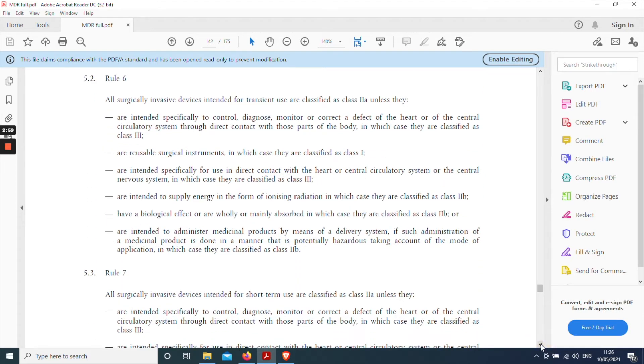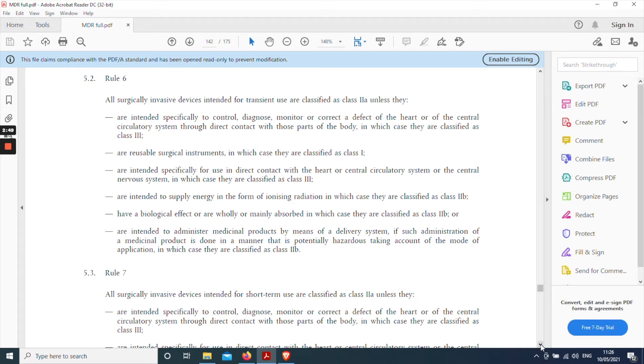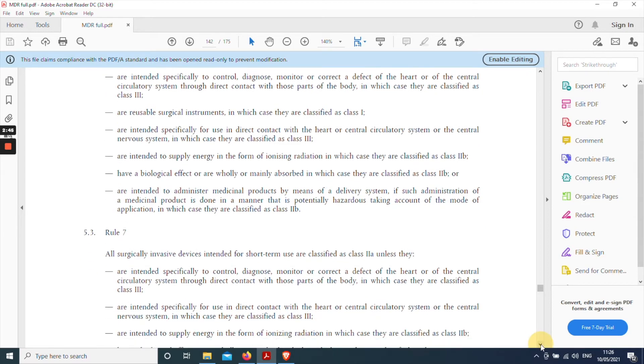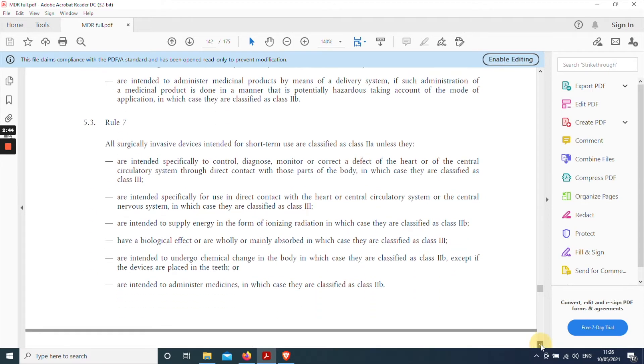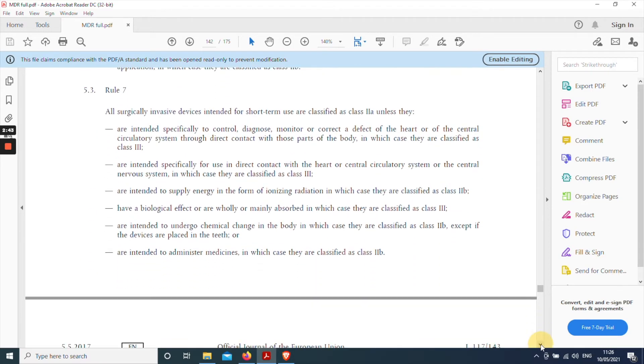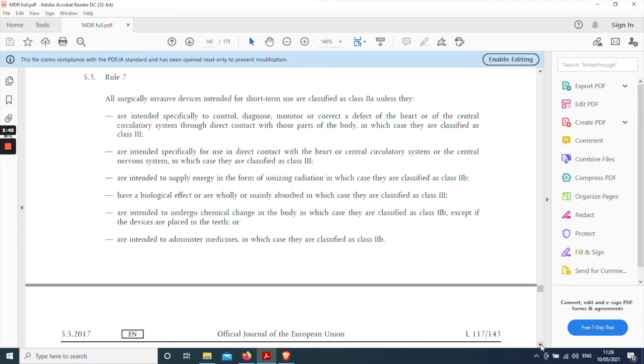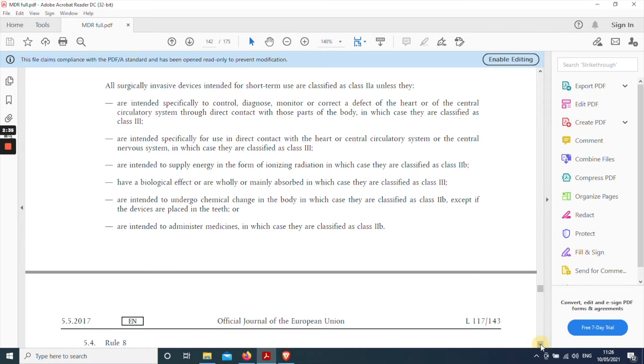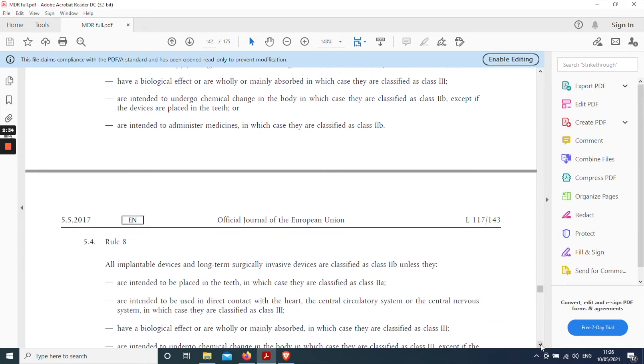This begins with all surgically invasive devices. So it sounds relevant so far intended for transient use. A pacemaker is not intended for transient use. It's permanently implanted. So again rule six can be disregarded on that basis. Move to rule seven. All surgically invasive devices intended for short-term use. Once again a pacemaker is not for short-term use. So we can disregard rule seven.